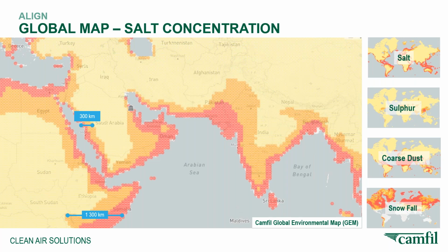So let's look at the salt content near the west coast of Saudi Arabia. You can see the high to intermediate levels of salt range from the coast inland to about 300 kilometers. So we really need to focus on exactly what that is per the location, because if we evaluate the east end of Africa near Somalia and Ethiopia, that high to intermediate range from the coast inland is approximately 1,300 kilometers. So it's really important to evaluate at exactly the specific point that we're looking at.